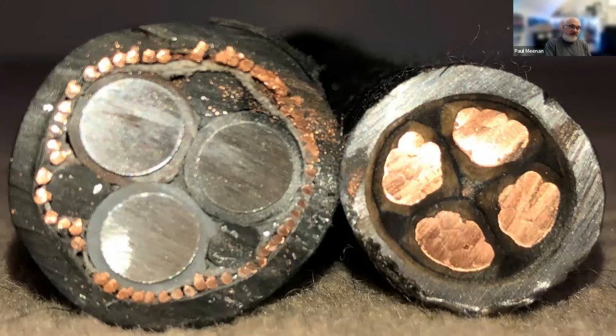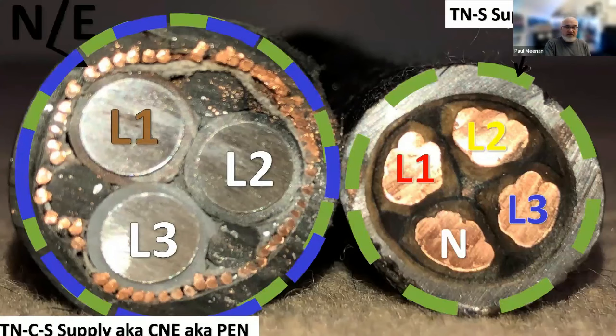And what you have is effectively three phases, L1, L2, L3, and a neutral. And the lead sheath is a wonderful low impedance earth conductor. The one on the left is the modern cable installed in the 70s, which had a 40-year design life. That's called a concentric. So what they did was they went with three phases aluminium, and then a copper armouring or sheath. And that's the neutral and earth combined. Hence, in that photo, they split the neutral and earth.